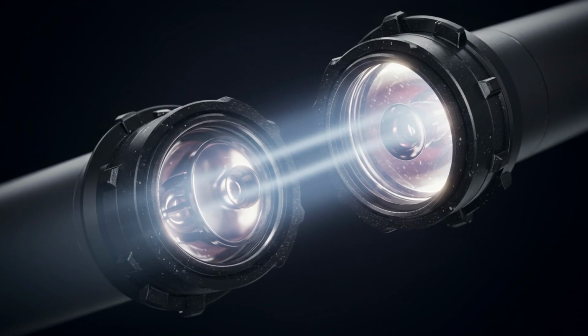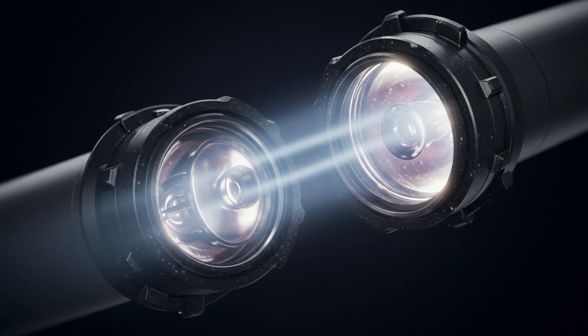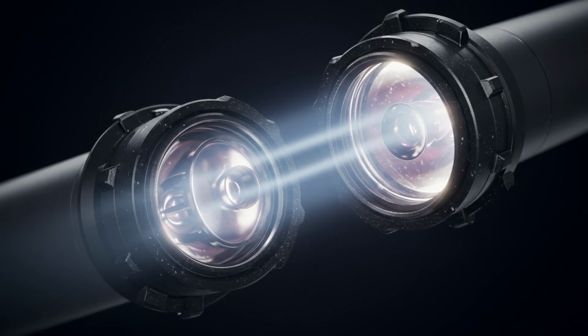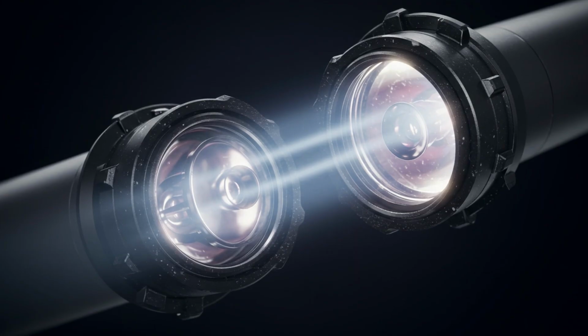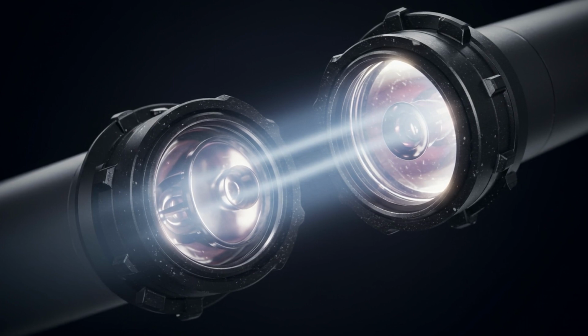At the tip of this long, slender tube are two high-resolution CMOS sensors, often smaller than a grain of rice. These sensors must withstand the brutal heat and pressure of an autoclave, the machine used to sterilize equipment at over 270 degrees Fahrenheit. Surrounding the lenses are fiber-optic bundles that deliver intense, cool light into the dark recesses of the human body. The image is processed by a dedicated video tower, which aligns the two views to create a perfect 3D image for the surgeon.